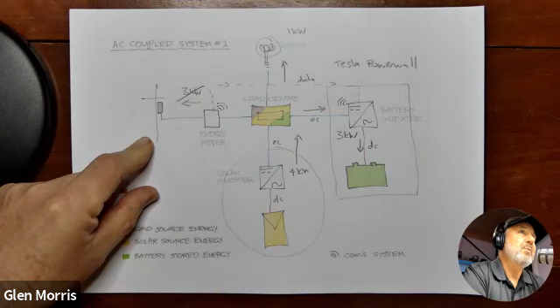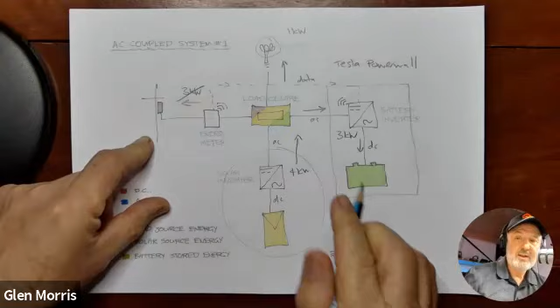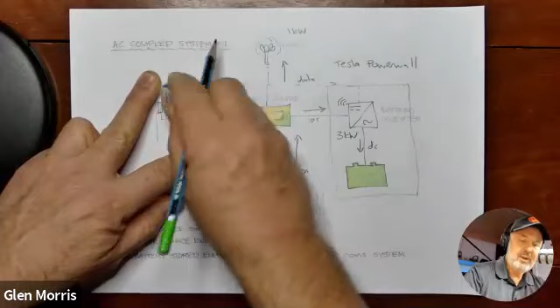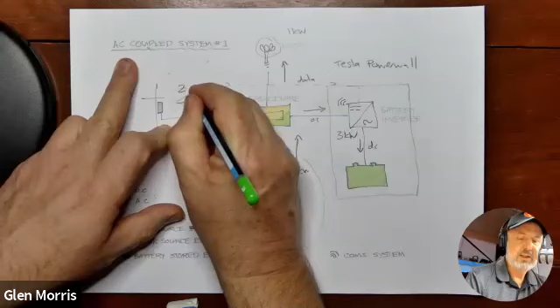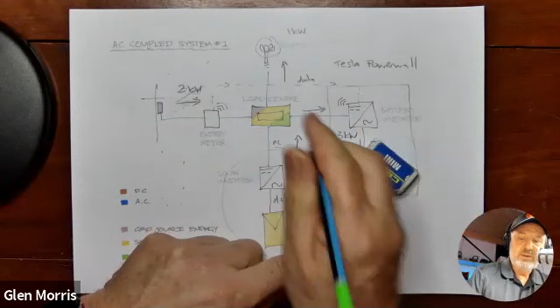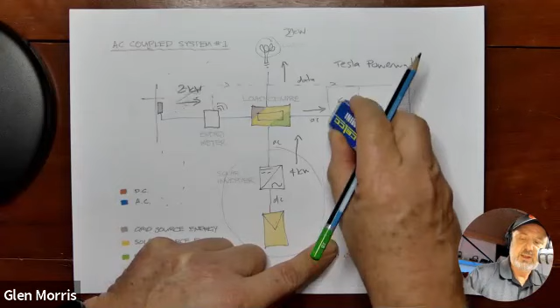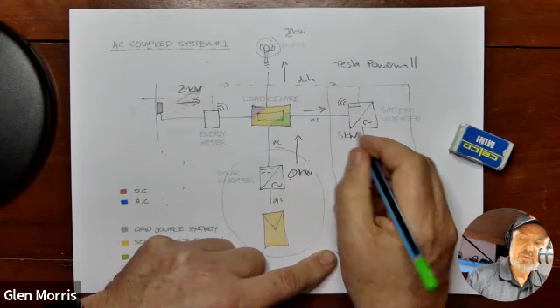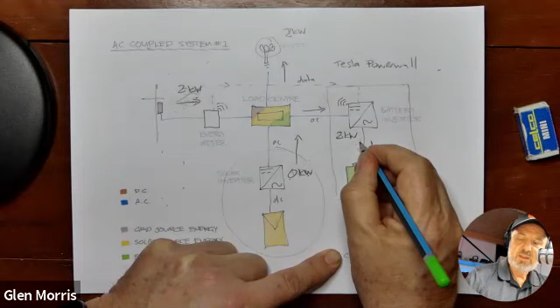The reverse is, and typically at night time or whenever there's a mismatch between solar generation and what the loads are consuming, it will reverse that process. It will, for instance, see that we're no longer exporting energy. We actually start to consume it. So energy's starting to go this way. So we're seeing 2 kilowatts of consumption. So at this point, it knows that, so we've got 2 kilowatts of consumption here. It's going to start exporting 2 kilowatts. So the solar's gone off because it's nighttime. So there's 0 kilowatts from the solar. And so now we've got 2 kilowatts coming from the battery, and it's going the other way. And so it's offsetting this energy that would have been drawn from the grid by reversing that direction of flow.